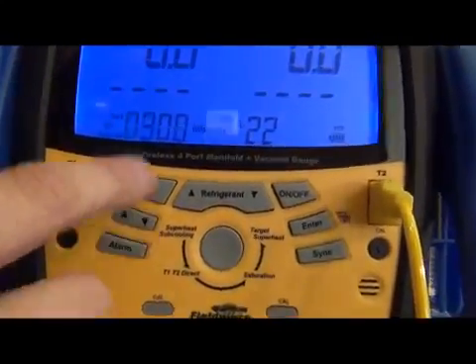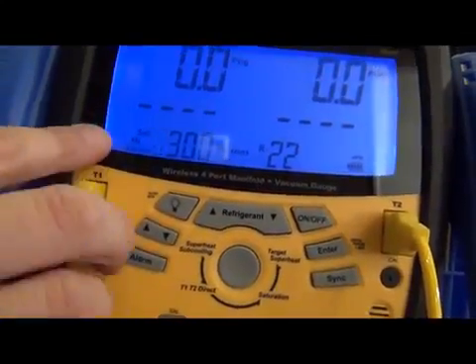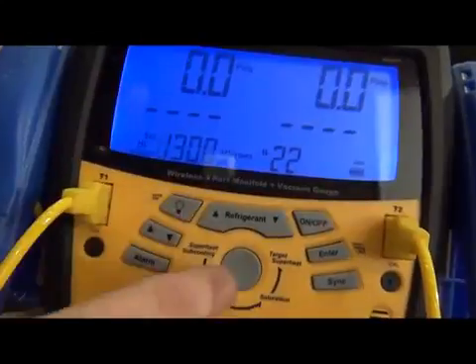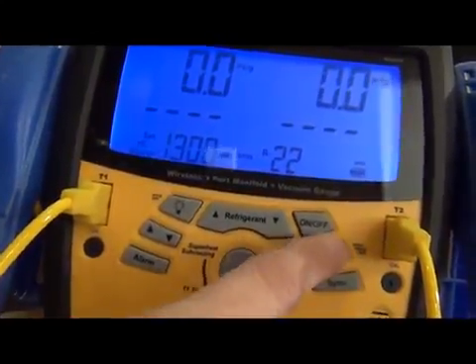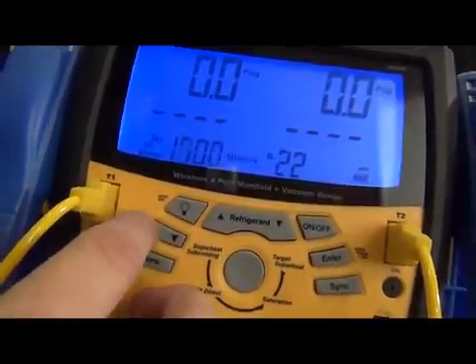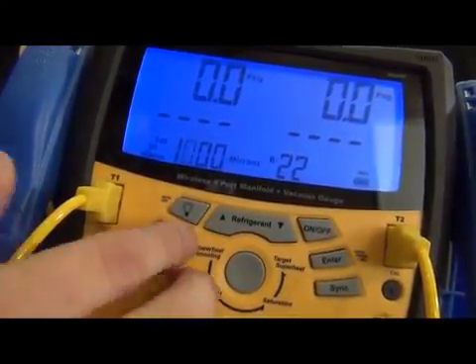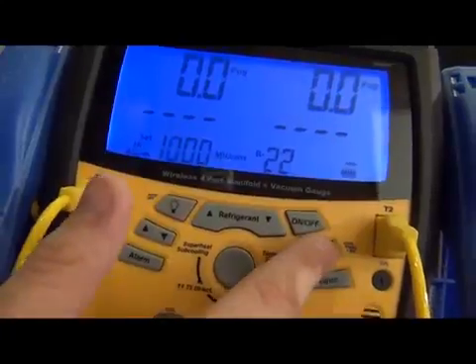So if I hold down the alarm button, it gets into the high alarm mode. What this is going to do is I can set this to, let's say, 1,000 microns, and after I go past, go below 1,000 and the microns start creeping up again, the alarm will go off at 1,000 microns.